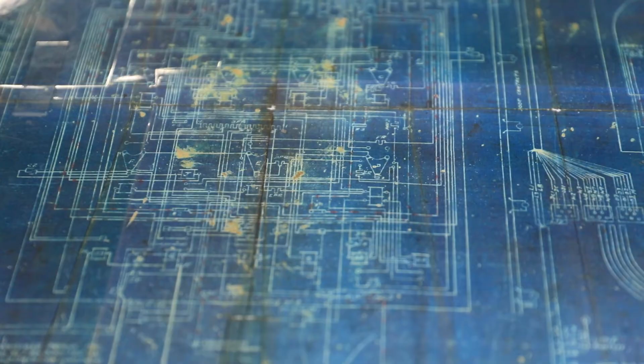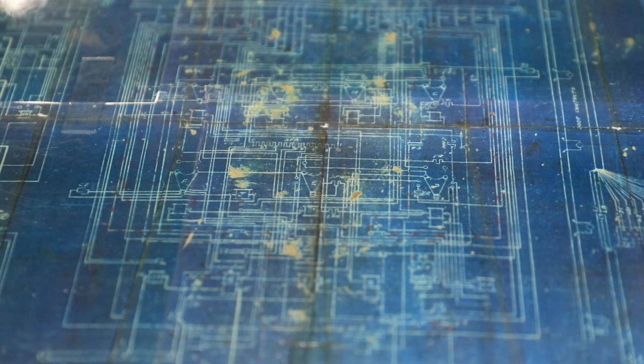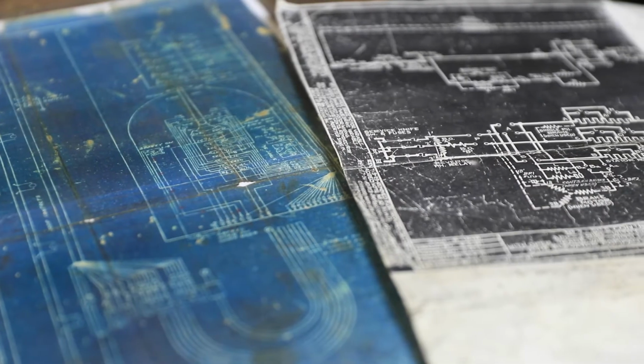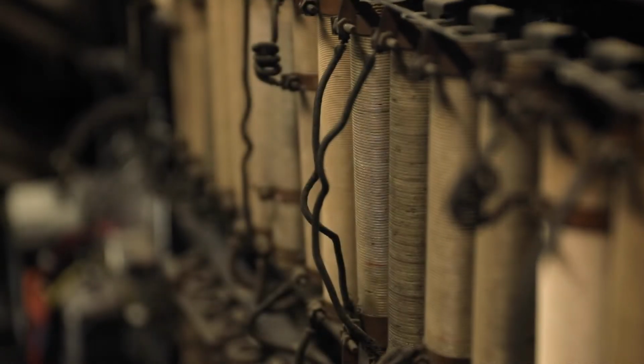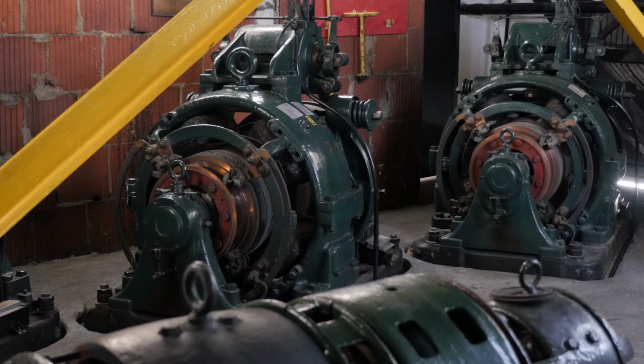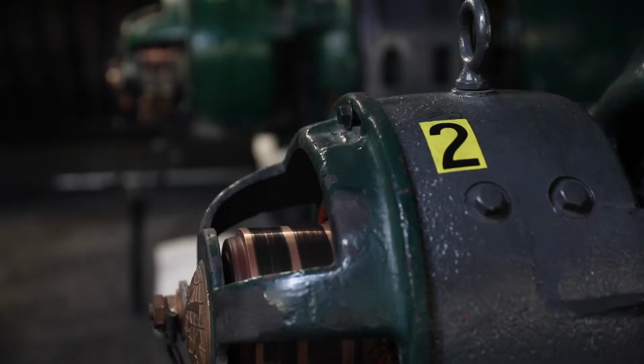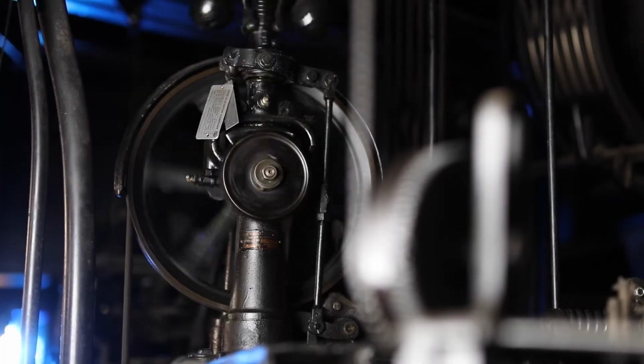They're gearless elevators, which literally means what it is. The motor directly turns a sheave, as opposed to a geared machine where you've got a worm gear turning a ring gear to make the elevator go up and down. These, you're just powering the machine, which means we have those very large machines that you've seen up there. They're roped 2 to 1, so you've got a rope like a yo-yo coming down over a sheave underneath it. That's the most common thing there is.